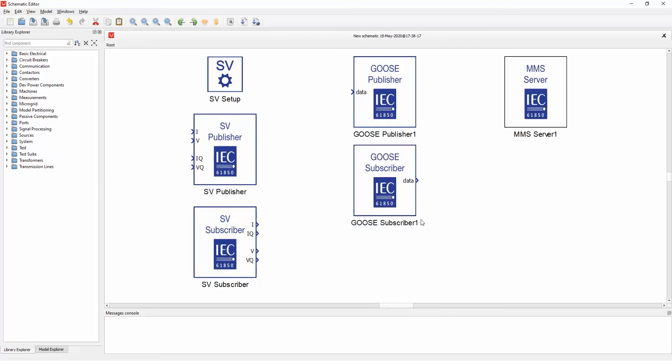For the Goose communication, it's a little bit different. You need to specify the configuration file, and the standard IEC 61850 standard specifies the ICD, SSD, and SCD files as the configuration file. So you need to specify these files in order to run the Goose communication.